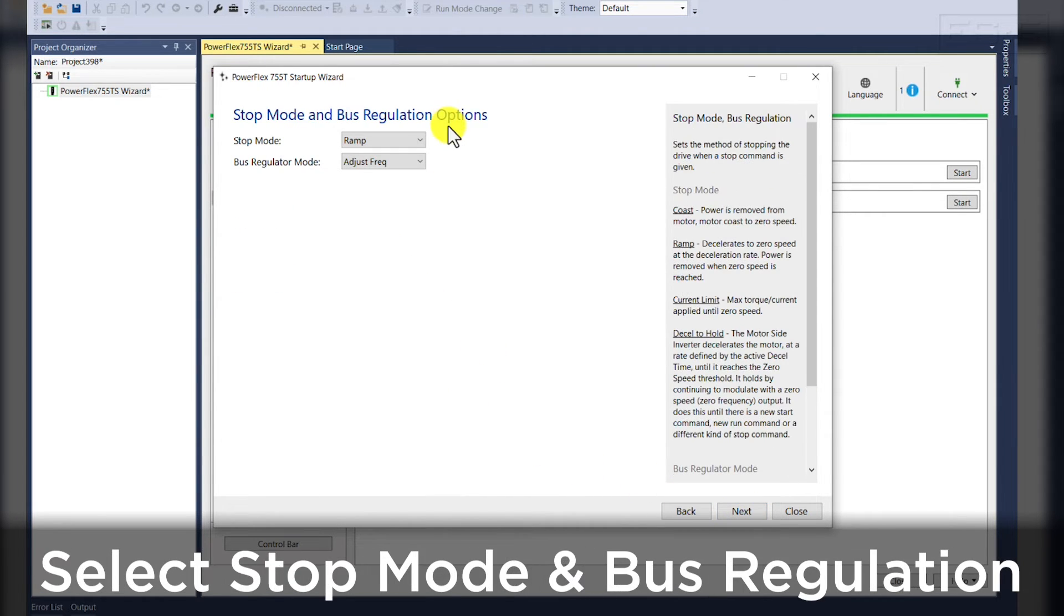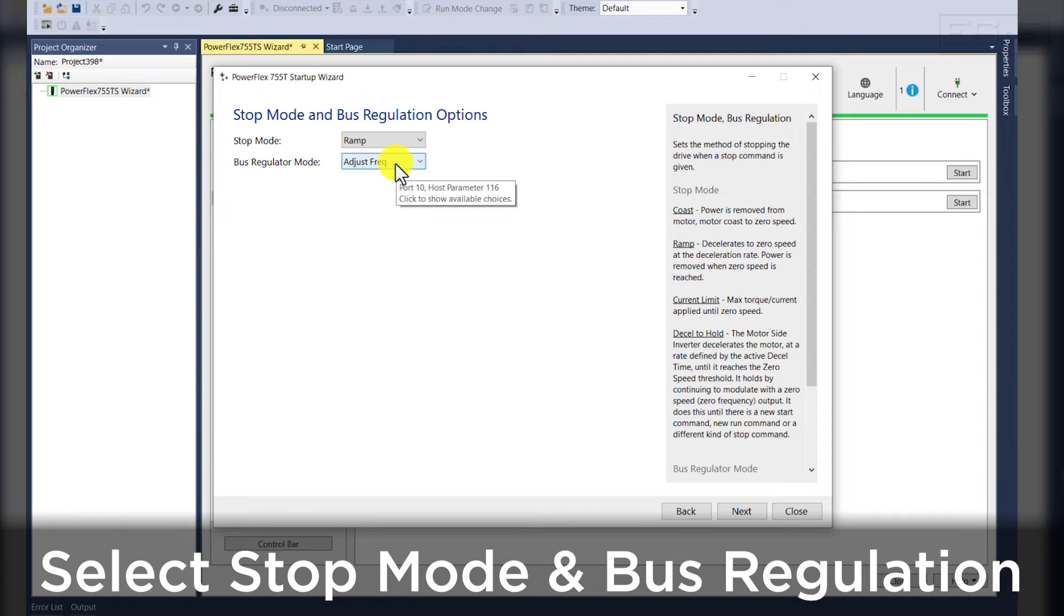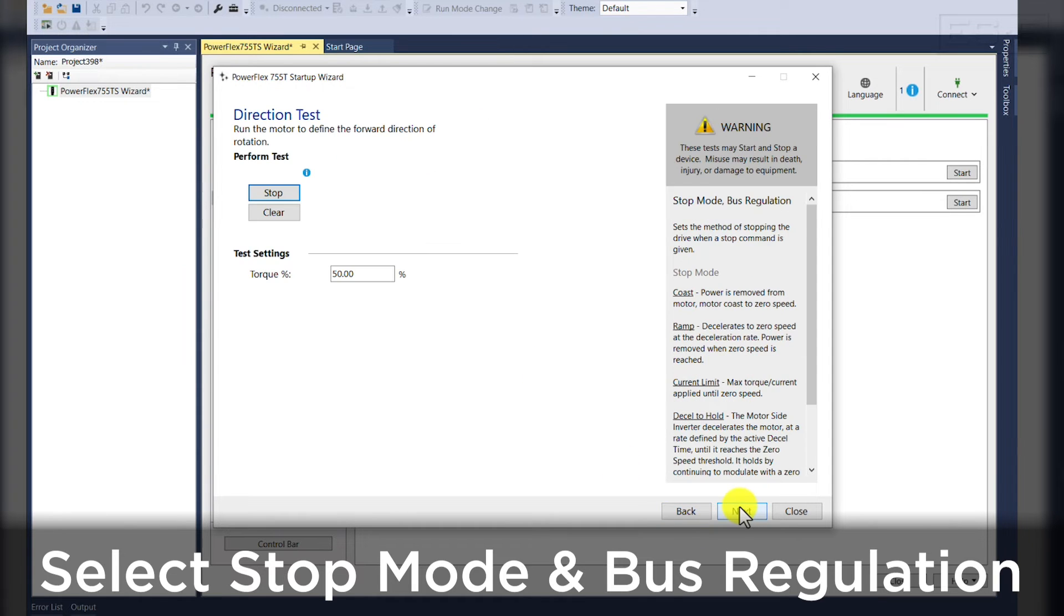Our stop mode and bus regulation options. So for this, we're going to use a ramp to stop and our DC bus regulator mode will adjust the frequency if we see that our DC bus voltage is getting too high.